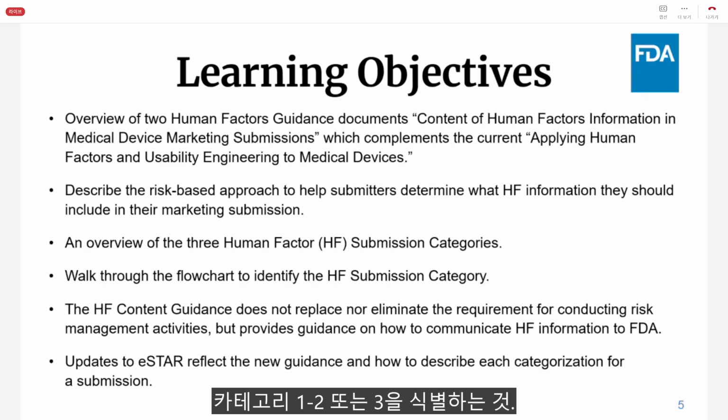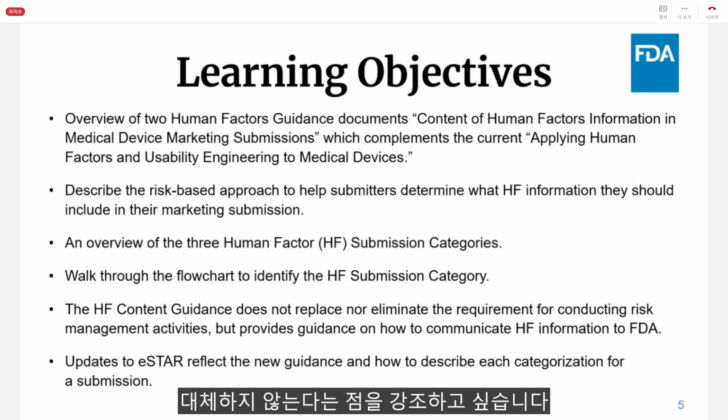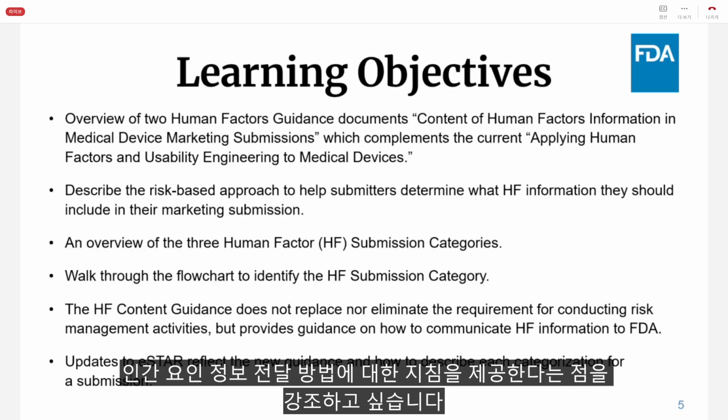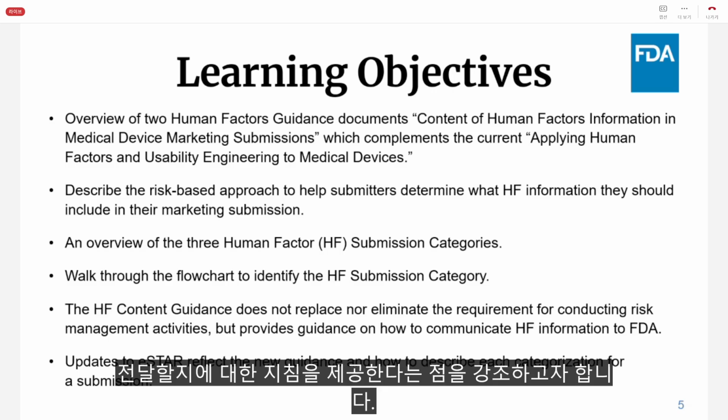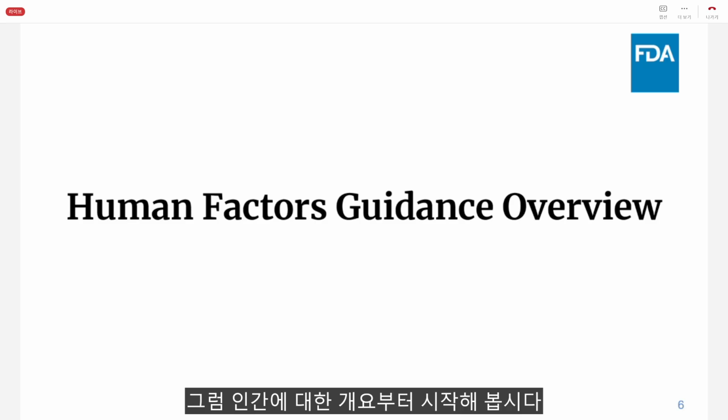Additionally, we want to emphasize that the Human Factors Content Guidance does not replace the existing Human Factors Guidance and does not eliminate the requirement for conducting risk management activities, but rather provides guidance on how to communicate human factors information and use-related risk management activities to FDA. Finally, we provide an overview of corresponding updates to eSTAR. So let's start with an overview of the human factors guidances.